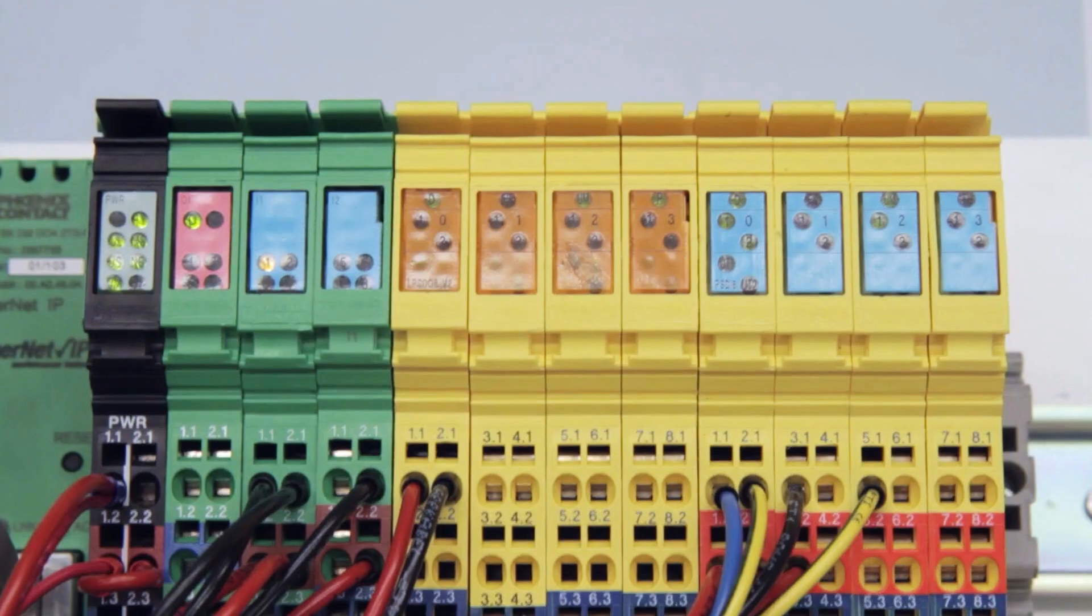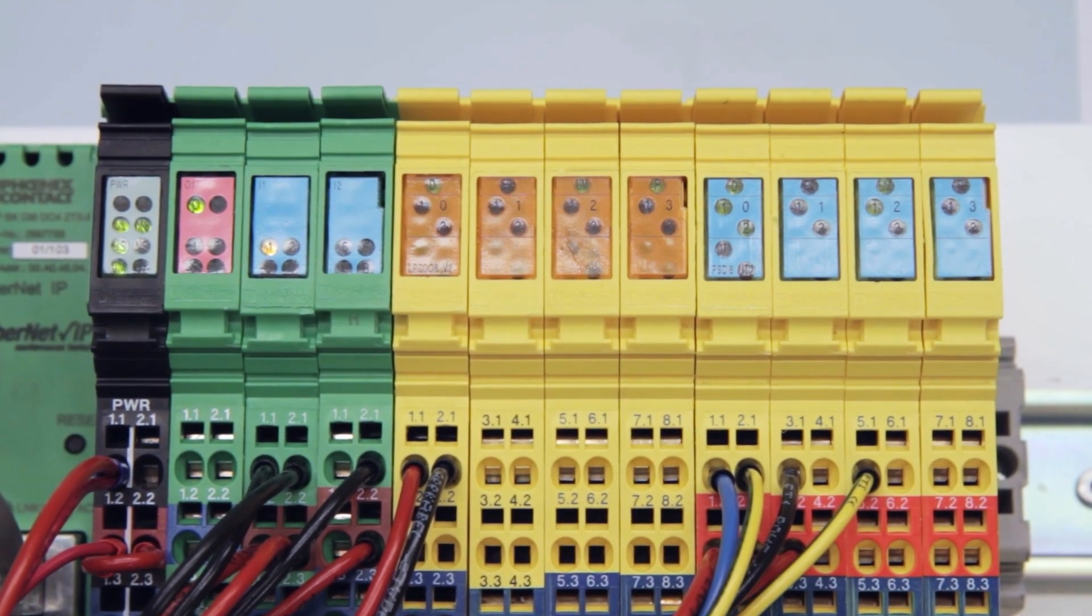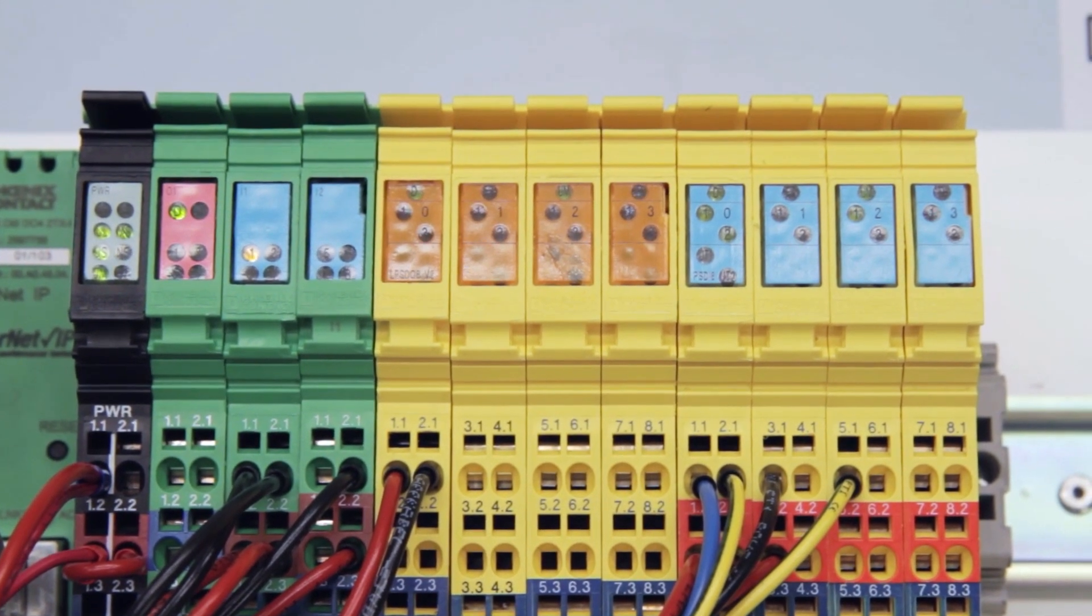Phoenix Contact has removed the need for a safety processor on the main PLC and distributed it in the I/O network. The Safety Bridge logic module is responsible for processing safety data, reading the safety sensor inputs from the safe input modules, and triggering safe outputs on the safe output modules.